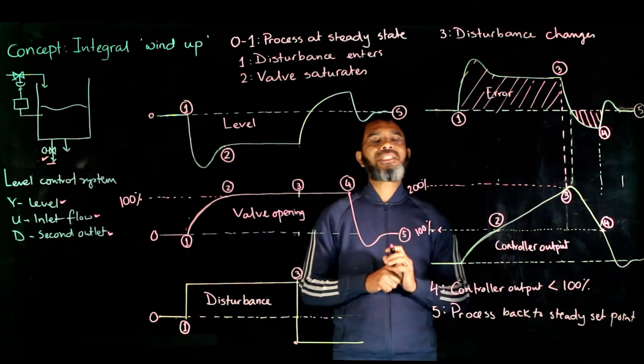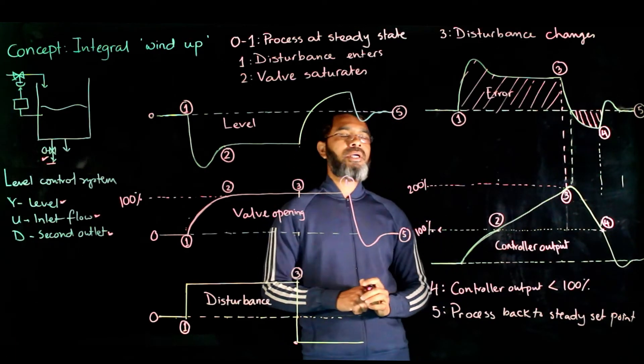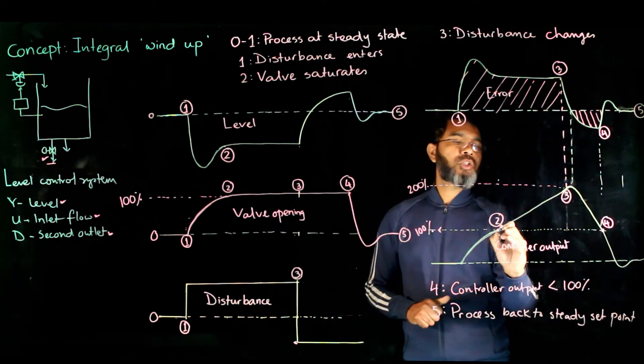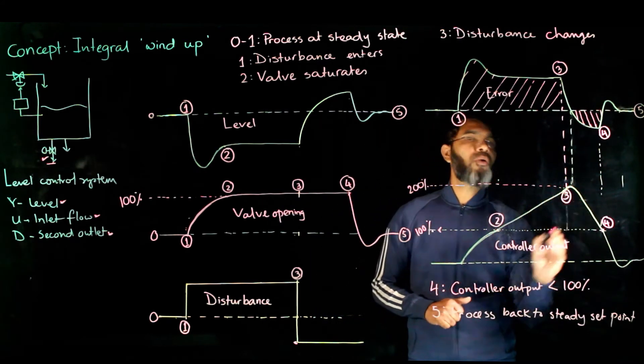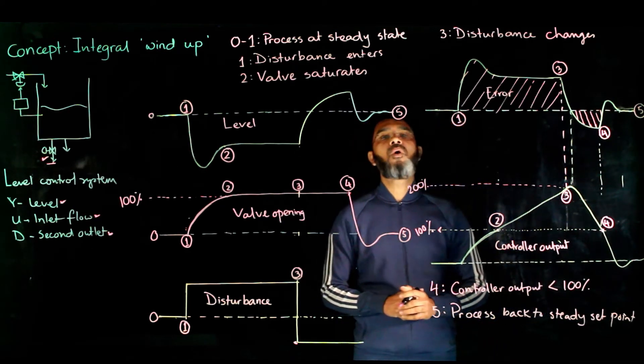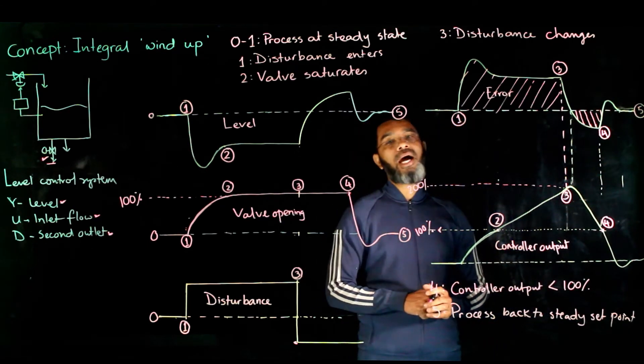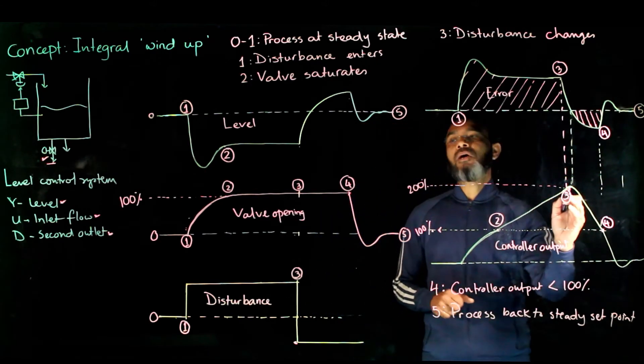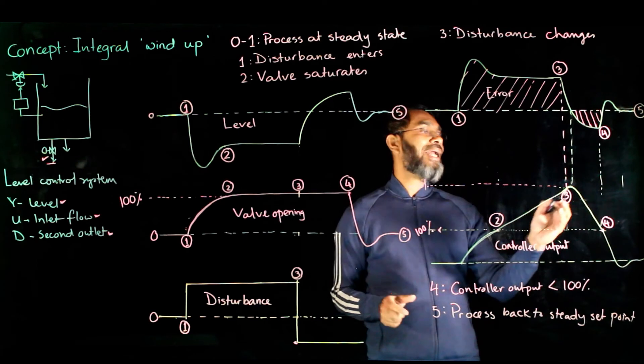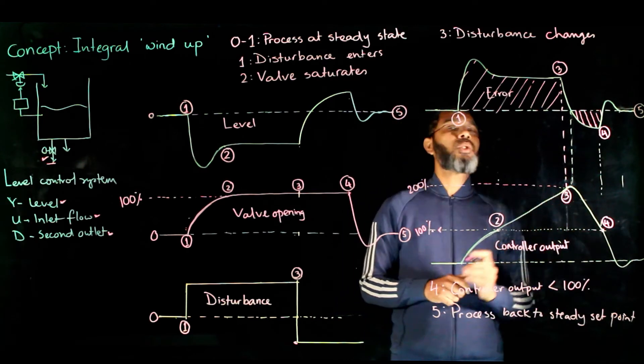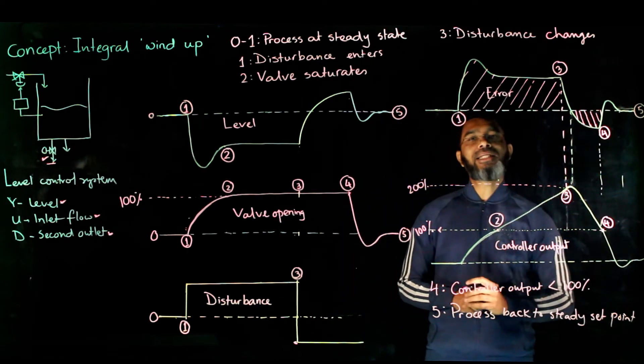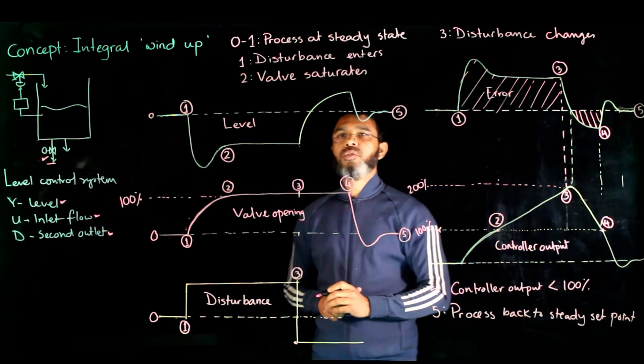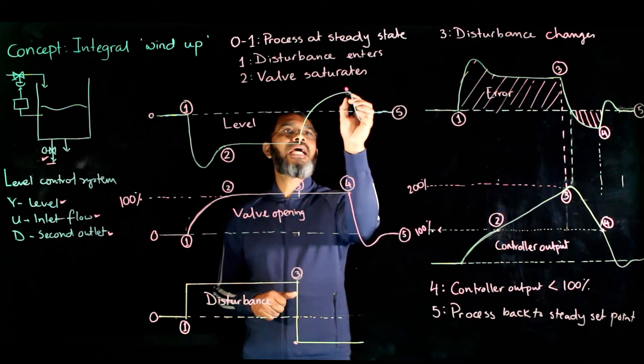This is what is called the windup situation: when the valve saturates, the controller keeps calculating the control action beyond 100%, and if that happens, the control action does not change until it comes back to 100%, meaning until a negative error occurs. Between instants 3 and 4, when the disturbance changed, the control action was supposed to reduce valve opening to bring the process back to set point, but that did not happen because the theoretical calculation was beyond 100%.